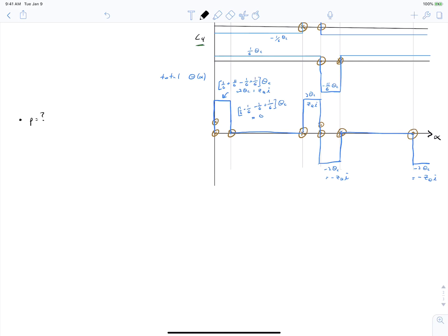And looking at this winding, it's hard to tell. I might guess that P equals 1, as in 2 poles, or maybe I would say, well, I've got a north pole here. I could imagine that this is kind of like a south pole, another north pole, south pole, north pole, south pole, or something, and I would say, well, there's 6 poles. In fact, it's virtually impossible to tell from this winding, so we'll say not clear. However, I will tell you that this is actually a single phase of a 3-phase winding that's used in a 10-pole motor. But you could not tell that by looking at this, or at least not from your training so far.